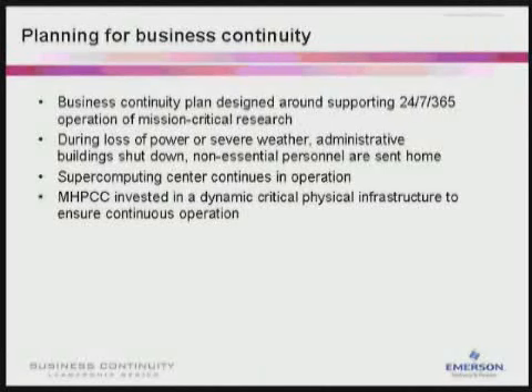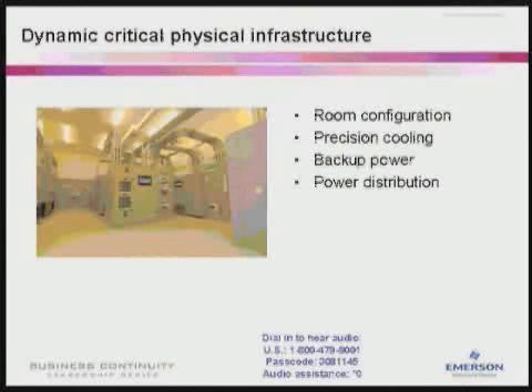Next slide. Our room configuration for our primary supercomputer is 40 racks in 4 rows set up in a hot aisle, cold aisle configuration. And one of the things that we were pretty smart in doing was putting in a 36-inch raised floor, which sure does help with the cooling. It prevents a lot of turbulence under the floor and makes it a lot easier to keep things cool in the data center.